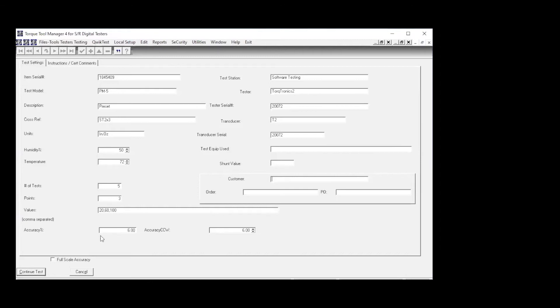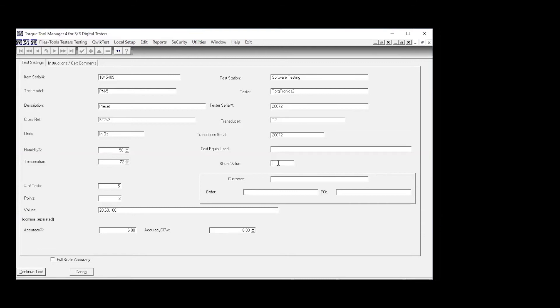So I'm walking you through everything. By the way, down here, the shunt value, we used to have a feature where we had a special resistor on the transducers. And that way, you could run a shunt test and make sure that everything was right where it should be. And things were right where they should be so many times that customers just simply stopped using it. So we don't really use that function anymore. And come down here and we have continued test. And in this case, we're going to close out of this because we have a separate testing video that we're going to take you to.